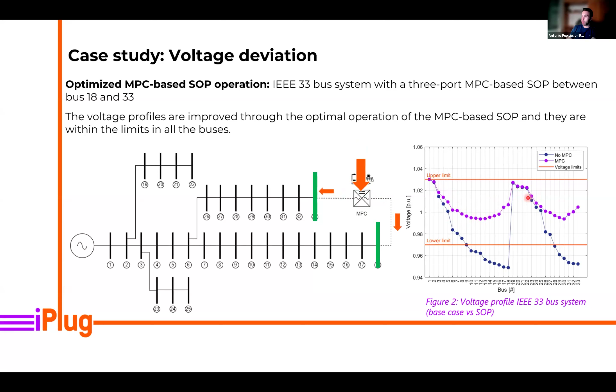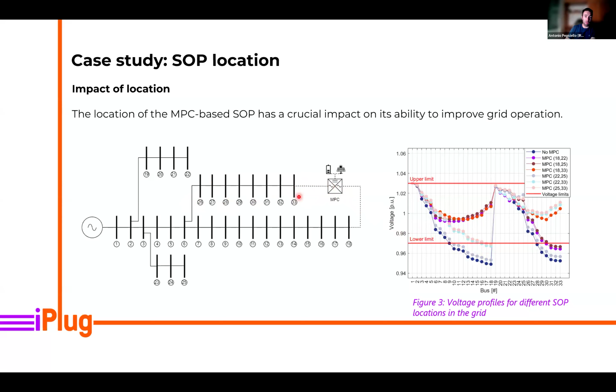We investigated what's the impact of having a soft open point in different locations of this particular system and in general in radial grids. And what we have seen is that it's very important to choose the correct location of the soft open point in order to maximize the benefit once we optimize its operation. For example, in this case, if we consider the gray curve, so multiport converter between bus 22 and 25, the improvement with respect to the base case is low. Unlike, for example, the current location between 18 and 33.